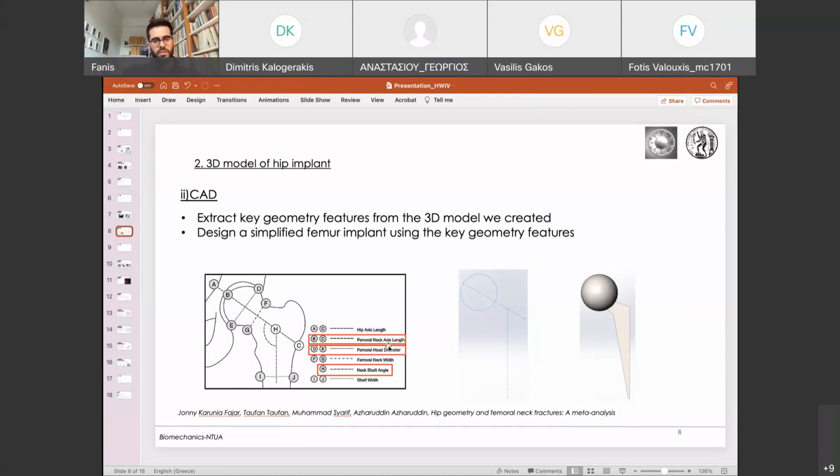The second dimension that we need to measure is the dimension BC, and generally define this axis. It's called the femoral neck axis. The reason for that is because this angle is very important in order to fit, and also this length. Okay, guys, so we know how much offset we have from, let's say, the axis of the femur bone to the end of the ball or to the center of the ball. You can measure whatever you want.